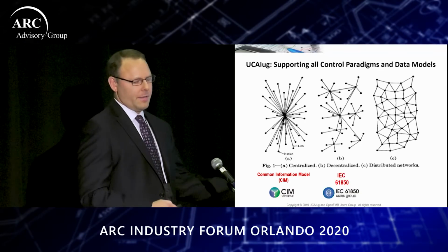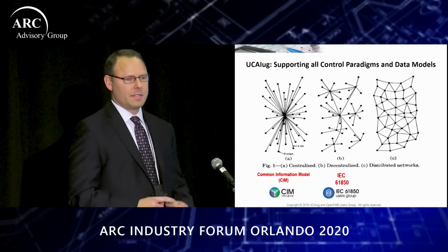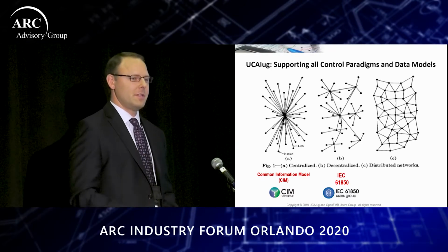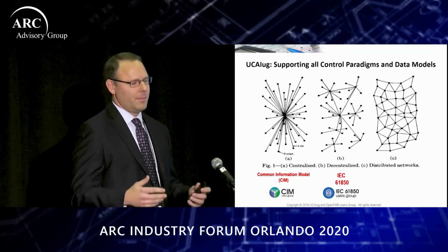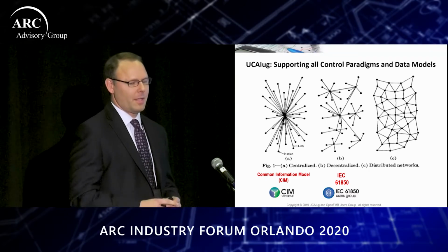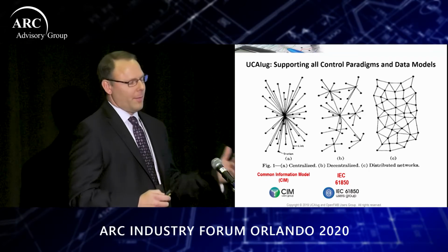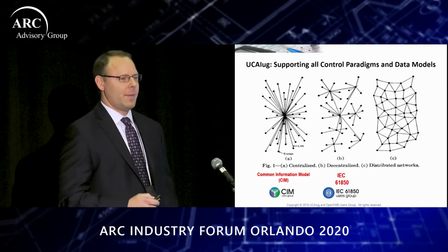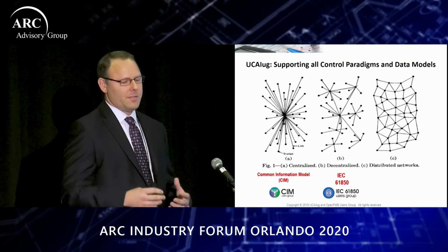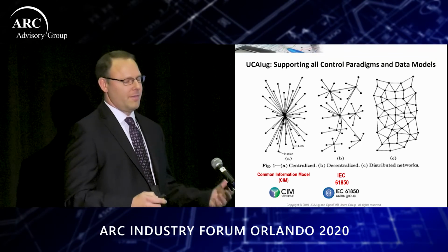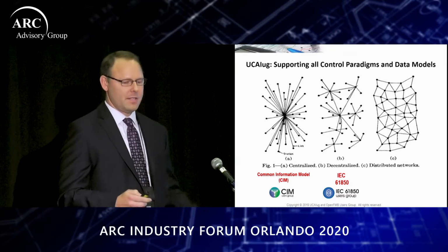The other standard, which popped up about a decade ago, is IEC 61850, really designed for substations. It was built in Europe, so it has a very different grid topology than we have in the US. That one is more of a decentralized paradigm, where each substation is not coordinated, but the devices have a very rich data set.